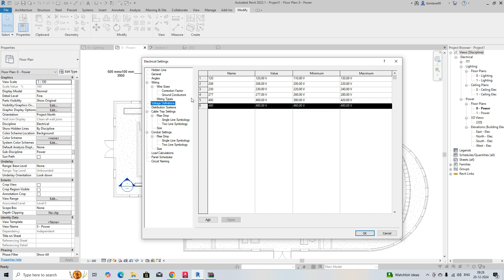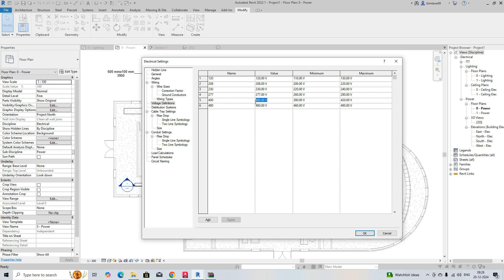If you want to add something — we already added this one. If you need to add 400, you just need to add 400, with a voltage value of 400, minimum value 380, and maximum value 420. Similarly, if you have a 480, just add 480 with minimum value 460 and maximum value 490. You can add 230 the same way.